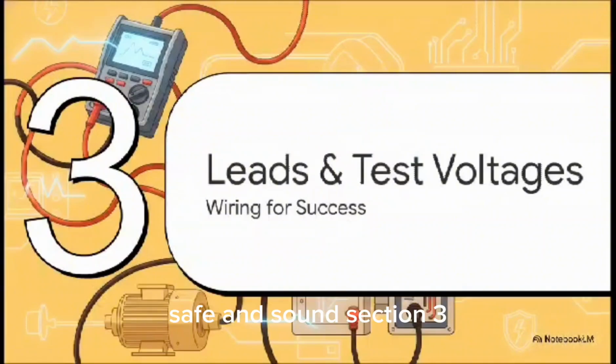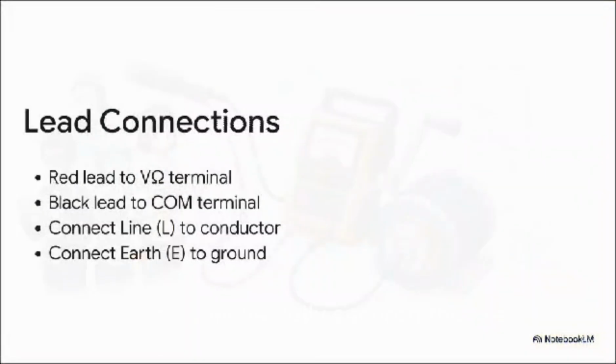Okay, safe and sound. Section 3, setting leads and test voltages. Assuming we've fully secured the area, let's methodically walk through how you physically wire up your meter for a successful test. For all measurements on these meters, you're going to connect your red test lead right to the V-ohm input terminal, and your black test lead goes to the COM terminal. Now, when you take those leads over to the equipment you're testing, you connect your line terminal, which is your red lead, directly to the conductor itself. Then connect the earth terminal, that's the black lead, straight to the ground. Actually, if you happen to be testing an industrial motor, that black ground lead just connects right to the grounded metallic motor frame.